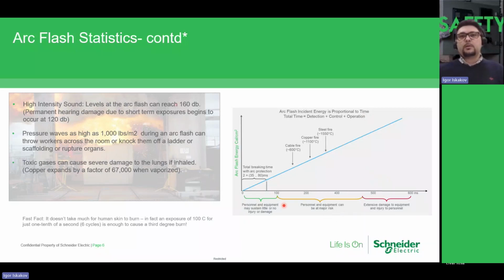So in these circumstances, we say that in the area from 0 to 100 milliseconds we should eliminate the arc flash. It means that we should stop the current on the bus bars and the supply to the burning arc flash. So we have approximately 80 to 90 milliseconds to open the circuit breaker. This time is also split into two parts. The first is the operational time of the circuit breaker. A modern circuit breaker takes an operational time of 35 to 50 milliseconds. Very old circuit breakers, like oil circuit breakers, take 80 milliseconds, even 100 milliseconds in some cases.